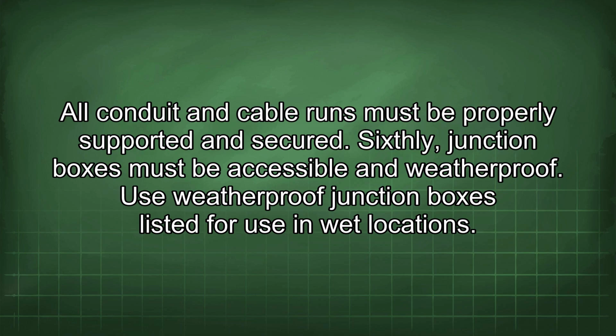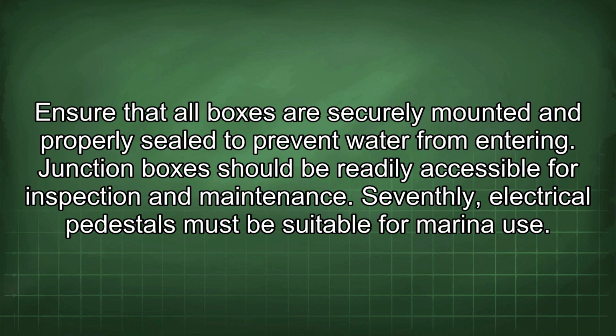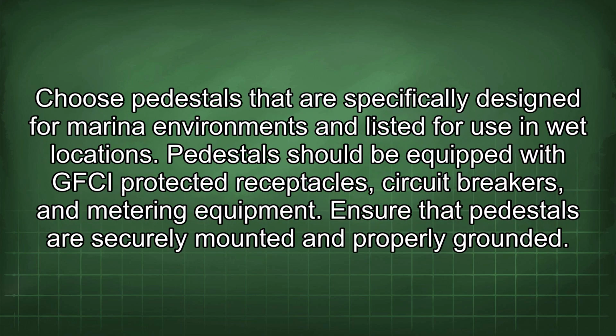Sixthly, junction boxes must be accessible and weatherproof. Use weatherproof junction boxes listed for use in wet locations. Ensure that all boxes are securely mounted and properly sealed to prevent water from entering. Junction boxes should be readily accessible for inspection and maintenance. Seventhly, electrical pedestals must be suitable for marina use. Choose pedestals that are specifically designed for marine environments and listed for use in wet locations. Pedestals should be equipped with GFCI protected receptacles, circuit breakers, and metering equipment. Ensure that pedestals are securely mounted and properly grounded.